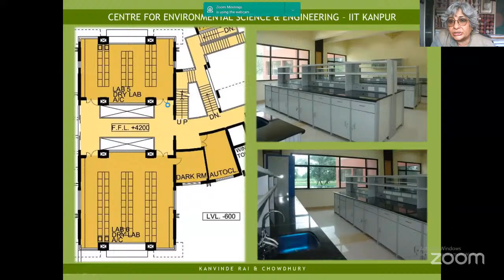Cooling through the earth air tunnel brought it down to 28 degrees. So the fresh air input we were giving into the AHUs was at 28, which made a huge impact on reducing the air conditioning load for the labs. The AHU sizes were substantially smaller as a result.